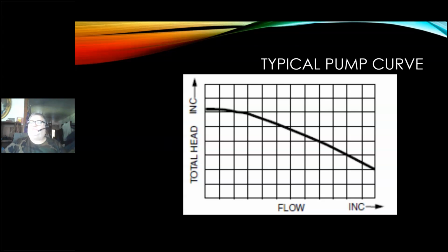The bottom left-hand corner is 0 for both of those lines. The curve, the dark thick line, represents the actual performance of the pump across those values. So the head increases from the bottom up, the flow increases from the left to the right. All right, so that's a simple pump curve.